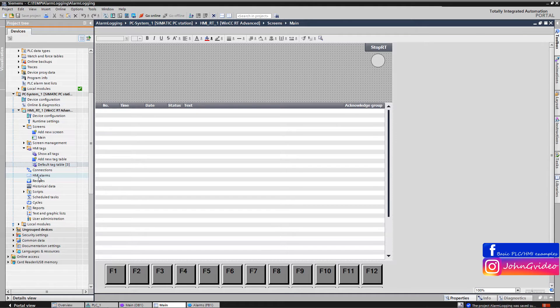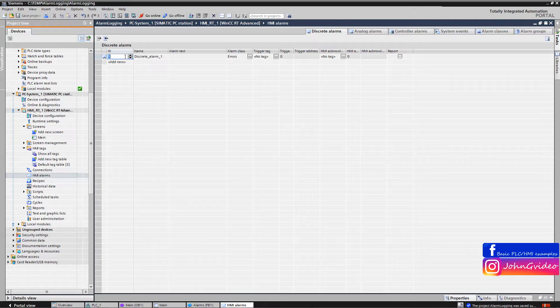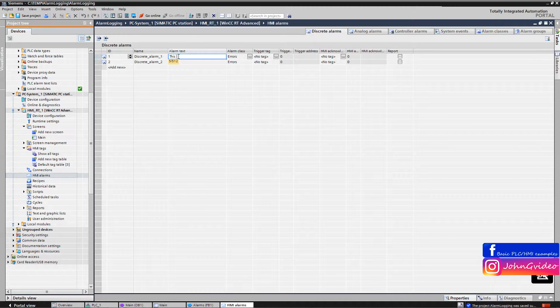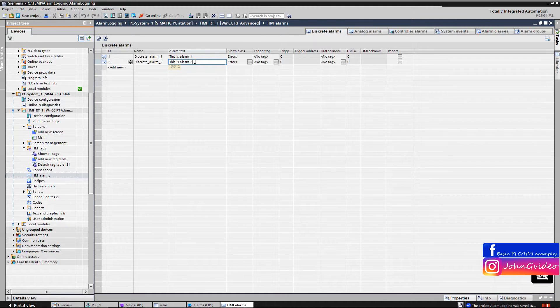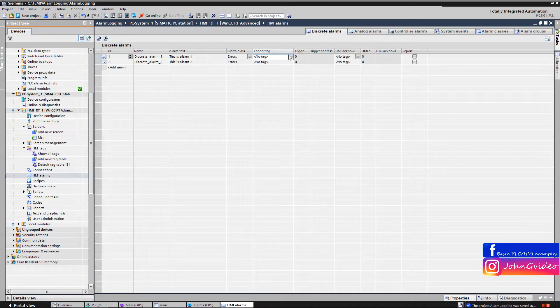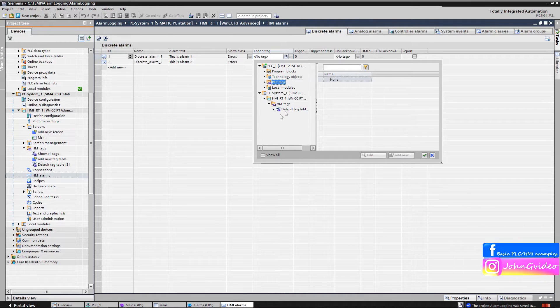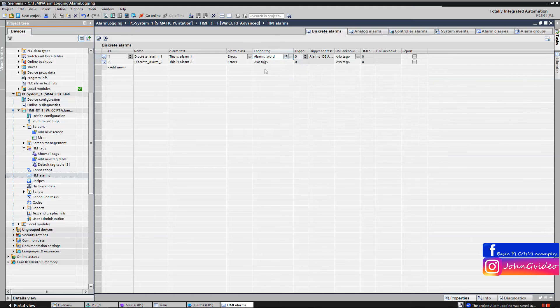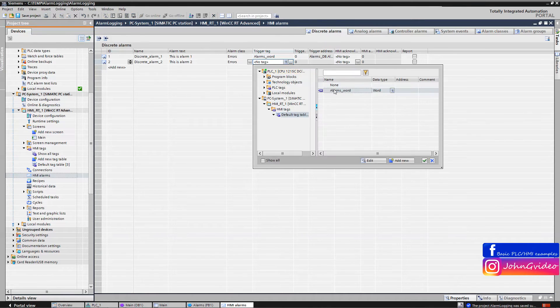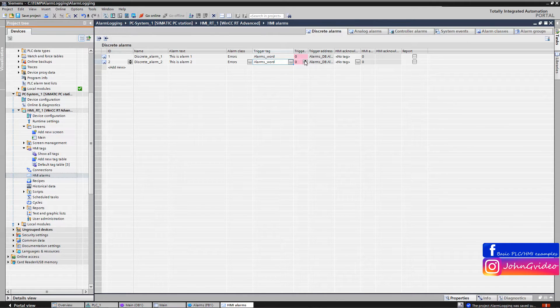After this we can define these two alarms in the HMI alarms options. We create two discrete alarms. Alarm number one will have the alarm text 'This is alarm one' and the second will have the text 'This is alarm two'. As the trigger tags for these alarms we use two bits which we activate in the PLC program — we use the created HMI tag 'Alarms_word'. The first alarm will have the trigger on the first bit, and the second alarm will have the trigger on the second bit of this alarms Word.